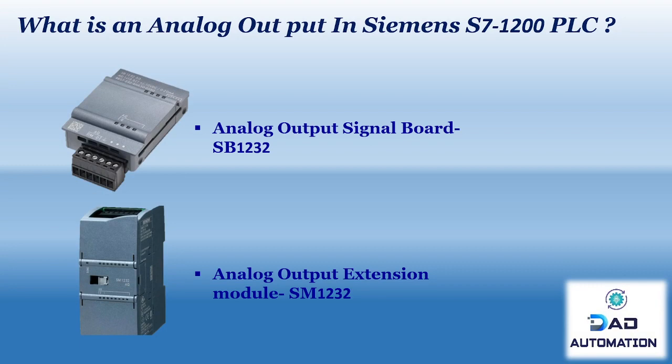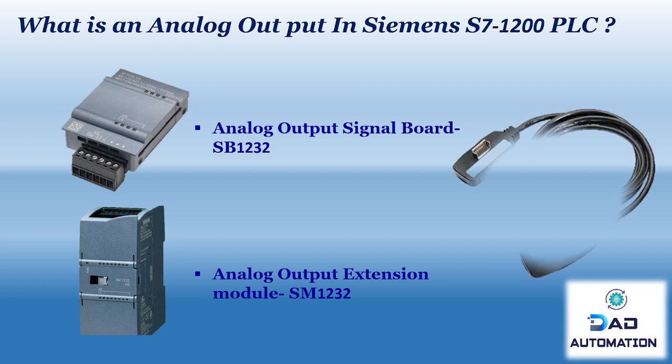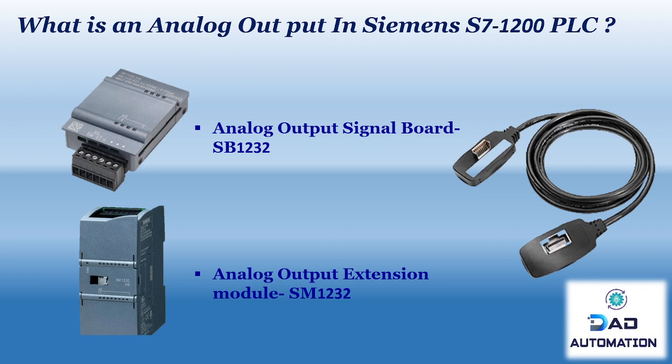What is an analog output in Siemens S7-1200 PLC? Mainly there are two types of analog output modules in the Siemens S7-1200 PLC. The first is the analog output signal board SB1232, which sits on top of the PLC, so no additional space is required due to its compact design. The second type is the analog output extension module SM1232, used when more analog outputs are needed in complex applications. An additional space in the control cabinet is required to install these modules. These modules can directly connect into the PLC by attaching the connecting port, and an expansion cable can also be used to connect them.